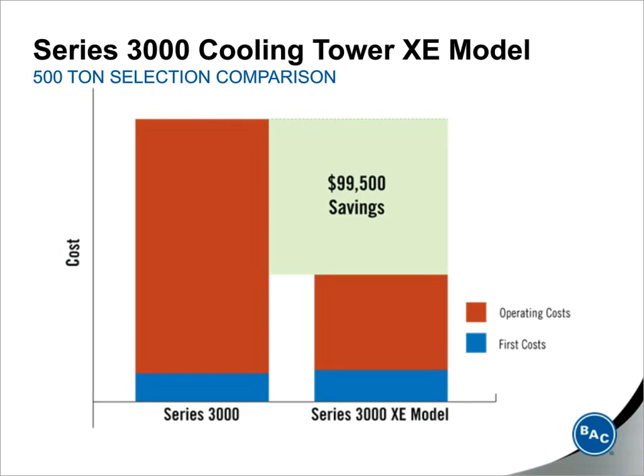And I keep touting extreme efficiency towers, so I do want to show the numbers. This particular example demonstrates how the reduced operating costs of an extreme efficiency cooling tower can benefit the owner over the life of the cooling tower. So by looking at these bars, the blue bars represent first cost. You can see that the extreme efficiency model is really only slightly more expensive than the lowest first cost model. Now, while the lowest first cost model has a 40 horsepower motor, the extreme efficiency model has a 20 horsepower motor, which again really offers half the operating costs.